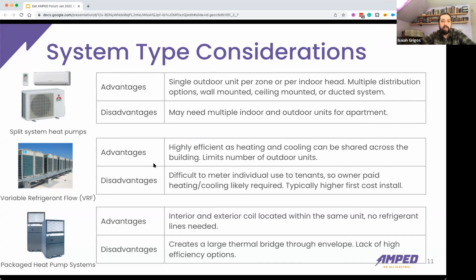Another nice thing about these is they reduce the amount of outdoor condenser units, so you're allowing for a lot more roof space for PV, as well as a lot fewer penetrations through your roof. I mean, you can imagine if you have a 60-unit building and you have 60 condenser units on top, one for each apartment, that's 120 penetrations through your roof. And each of those penetrations cost money to install and they can all leak. So VRF systems can be very popular just for those reasons alone.